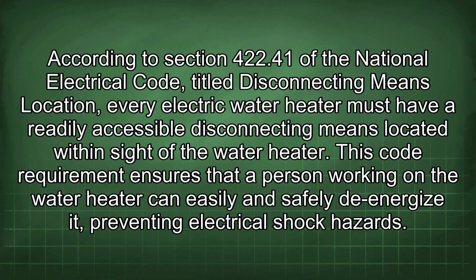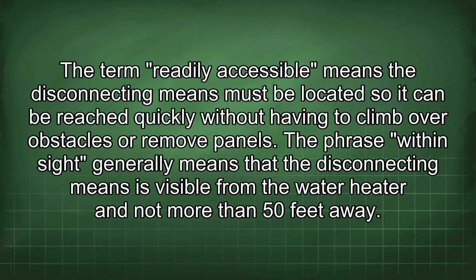According to Section 422.41 of the National Electrical Code, titled Disconnecting Means Location, every electric water heater must have a readily accessible disconnecting means located within sight of the water heater. This code requirement ensures that a person working on the water heater can easily and safely de-energize it, preventing electrical shock hazards. The term readily accessible means the disconnecting means must be located so it can be reached quickly without having to climb over obstacles or remove panels.